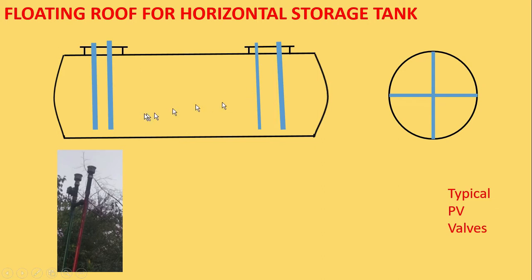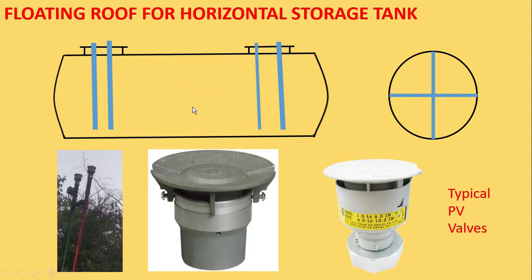Whenever pressure builds up inside the tank, gasoline vapour evaporates and is emitted to the atmosphere. And whenever there is vacuum or low pressure inside the tank, air is sucked in through this vent. This is the typical look of the PV vent, but even with it installed, we are still emitting gasoline vapour into the atmosphere, which is not good for the environment.